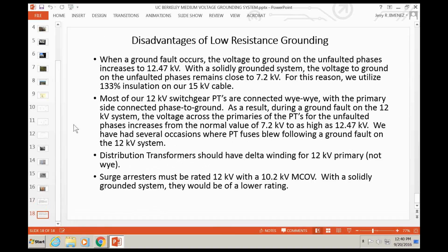Okay, so now I'm at the last slide, and the disadvantages. I actually thought of four. So here's one that most people know about. When you get a ground fault, the voltage to ground of the unfaulted phases increases to 12.47 kV, more or less. Maybe it may go a little higher because of a surge.